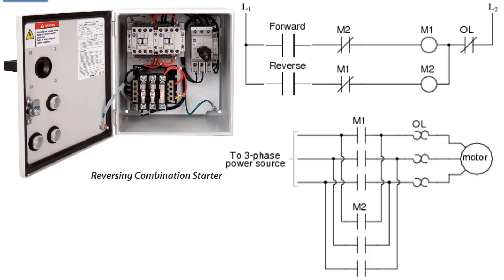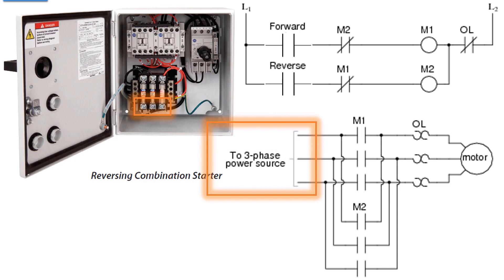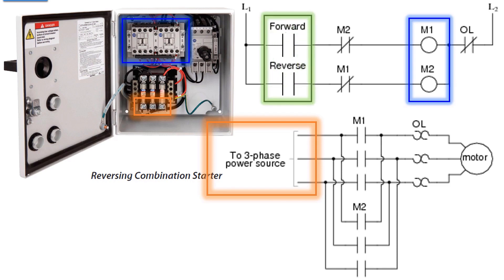Controlling a three-phase motor — I showed it with a starter. This is a reversing starter, which uses two starters. You have a three-phase power source connected at the bottom of those fuses in the panel. When you energize one of the two coils, M1 or M2, that closes the contacts that feed three-phase power to the motor. The difference between the three sets of contacts for M1 and M2 is that one of the phases for M2 is reversed from M1 — that's what makes it reverse. You control this with two outputs from a PLC.